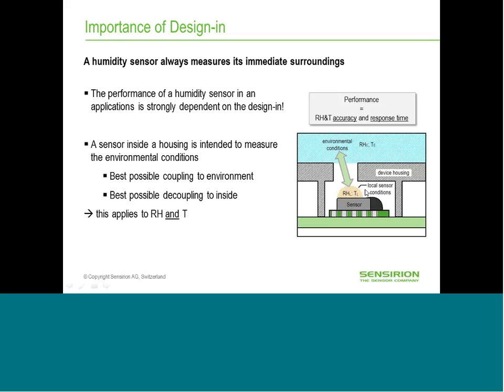As I said before, the sensor always measures its local conditions, the conditions right at the sensor, but it's intended to measure the environmental conditions. So you have to make sure by making a good design that the local conditions are as close as possible to the environmental conditions. This can be reached by best possible coupling to the environment and best possible decoupling from disturbing effects inside the housing. This applies both to humidity and temperature.